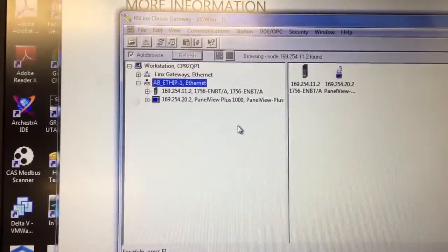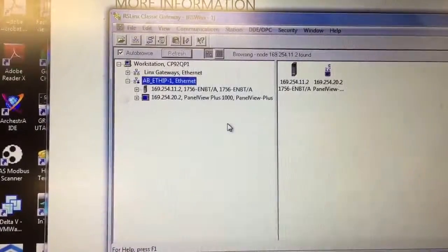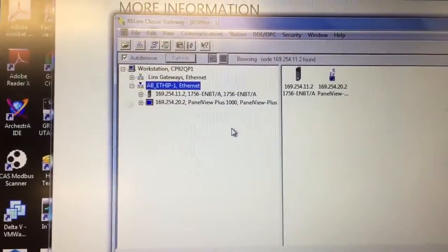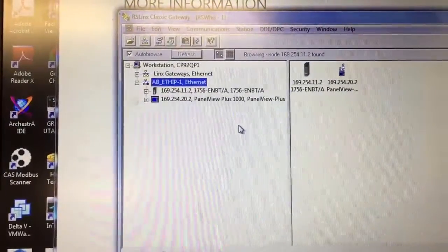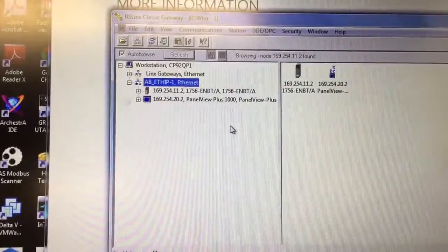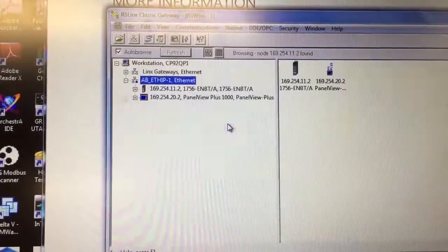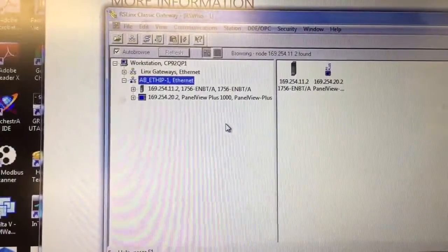This static IP address assignment is used quite frequently in industry, because if this IP address is changing, then we might not be able to find our device. It could have a new IP address when it's powered down and powered back up, if we had a power bump or anything like that. In any control system, it's good to use static IP addresses for this purpose.